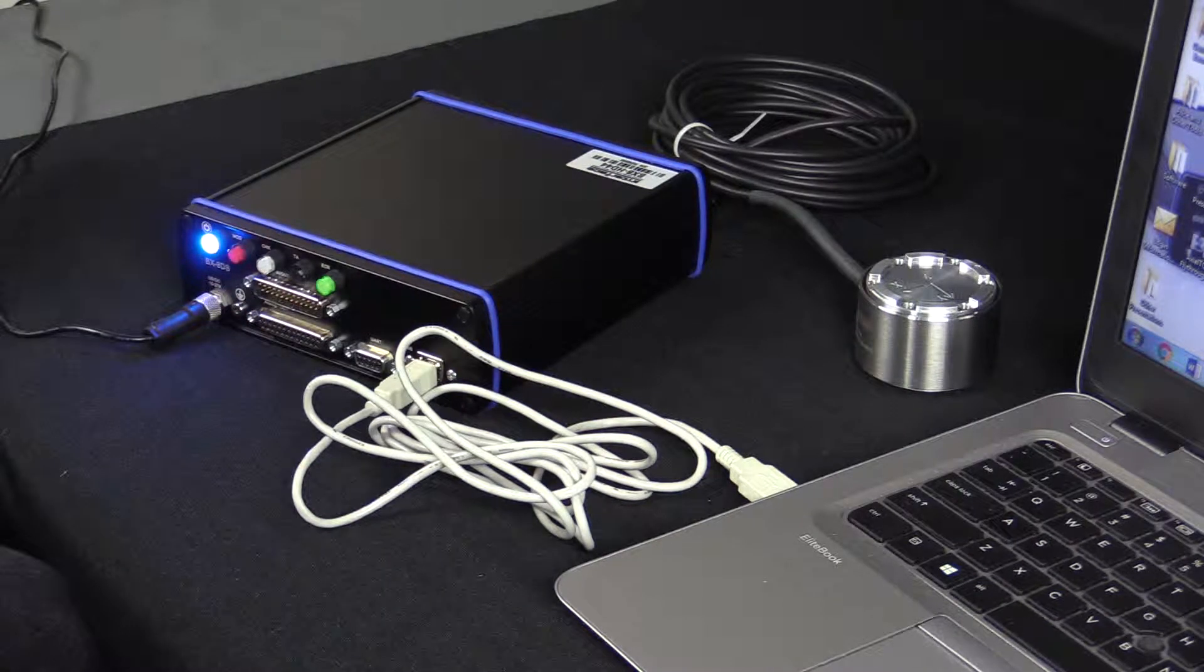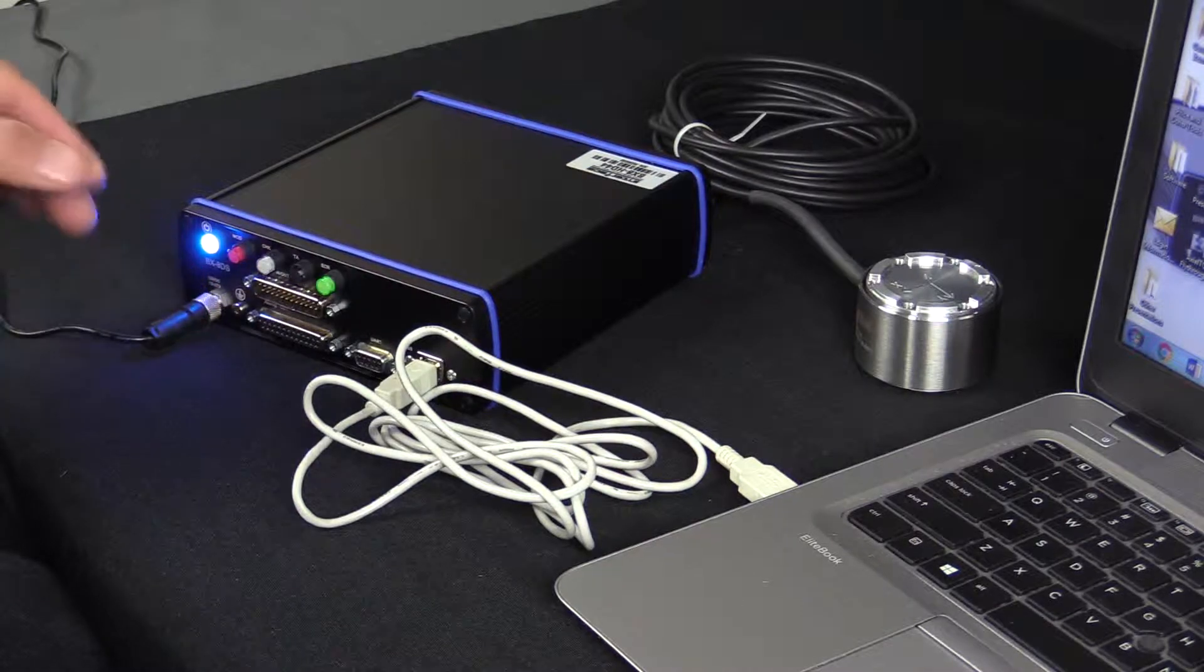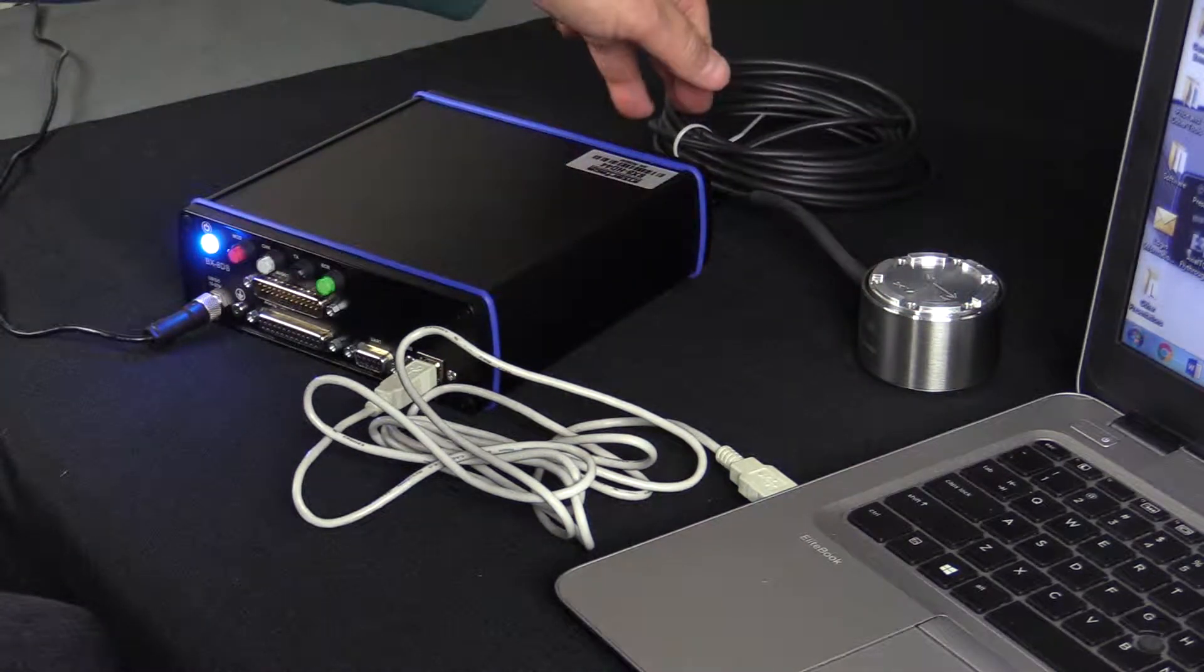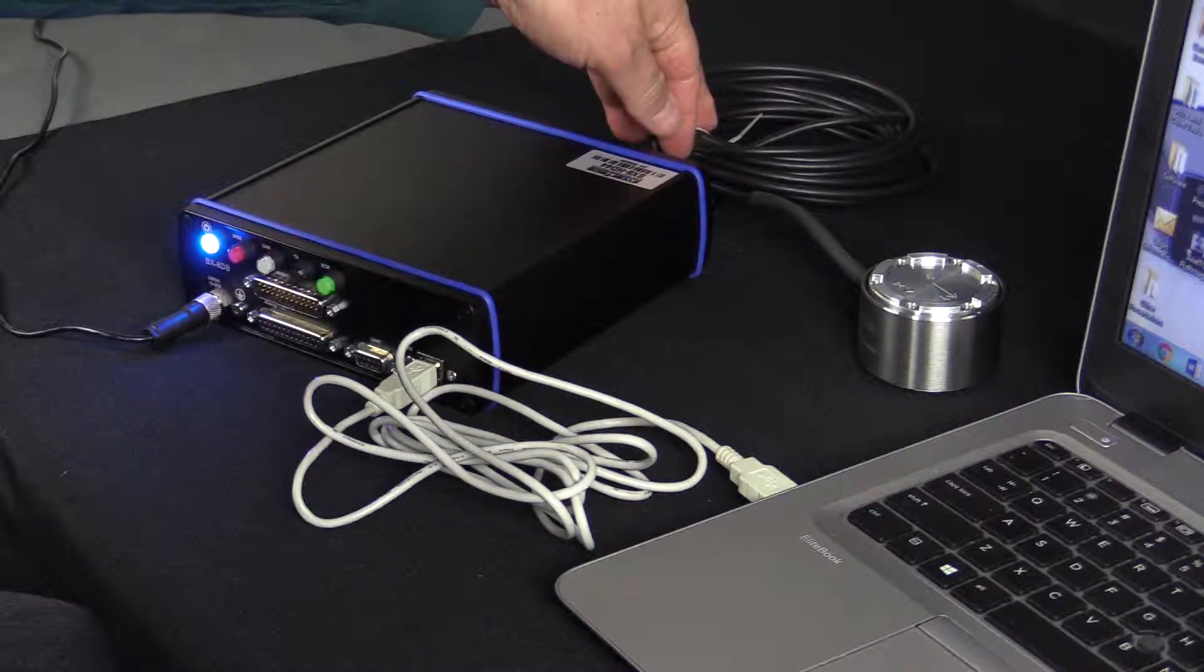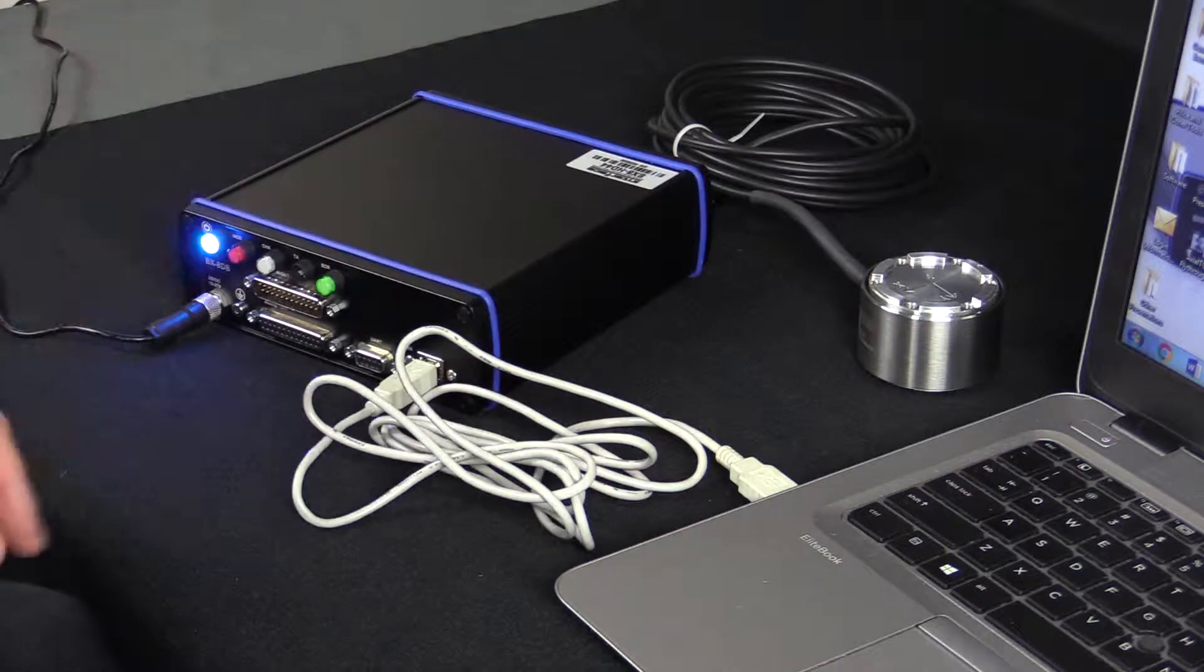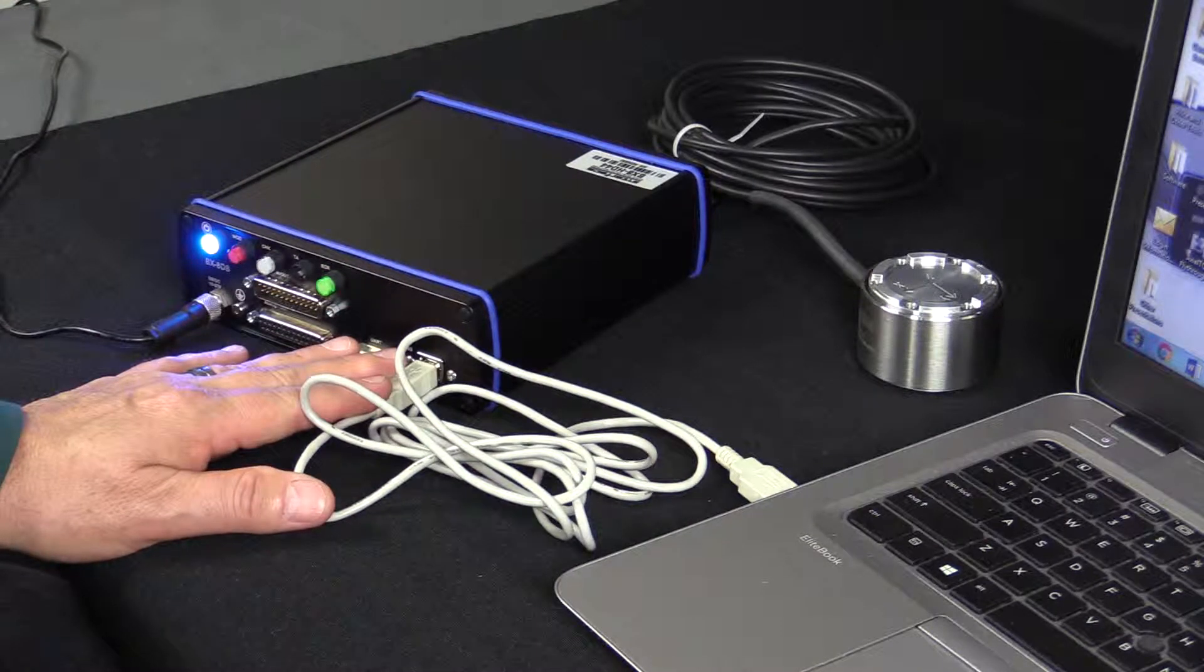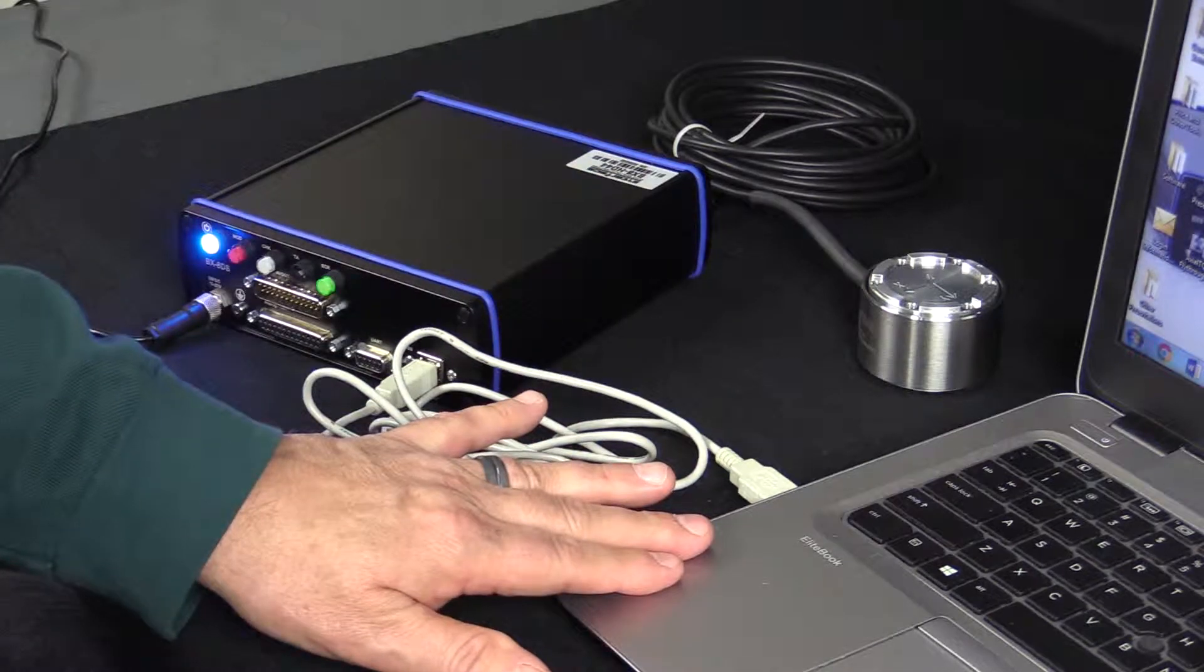We'll connect the power to the front of the BX8. We'll connect the 6-axis load cell through the 1-6 connector on the back of the BX8. That's for one 6-axis load cell. Then we'll connect the USB from the front of the BX8 to the PC.